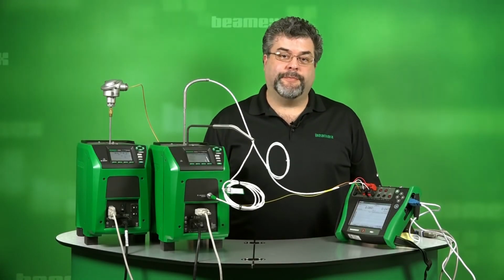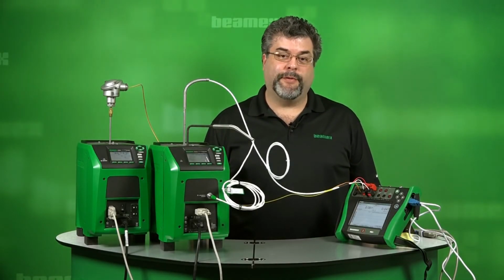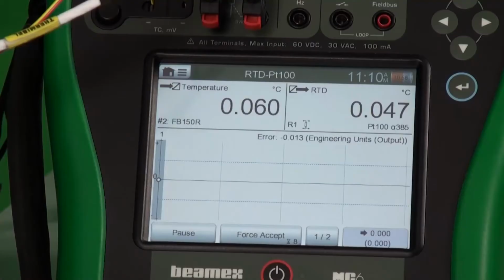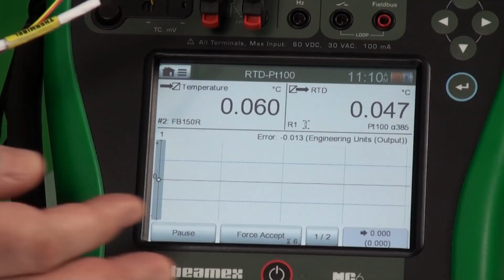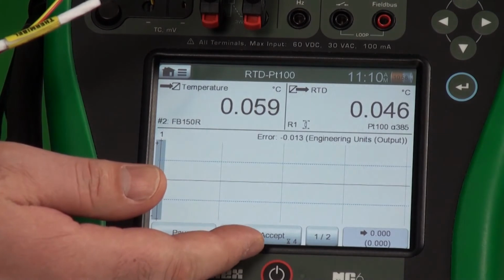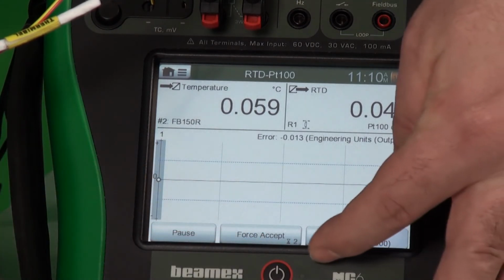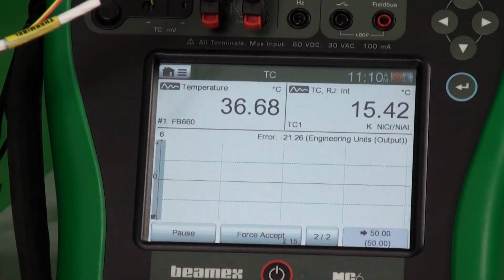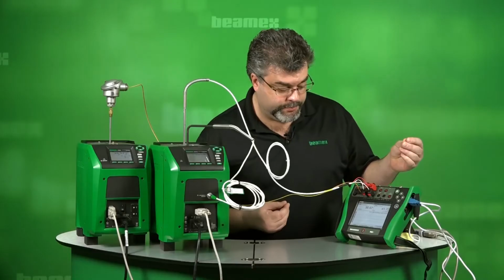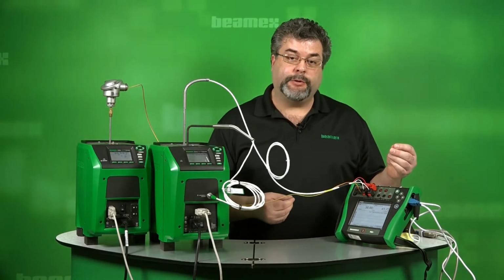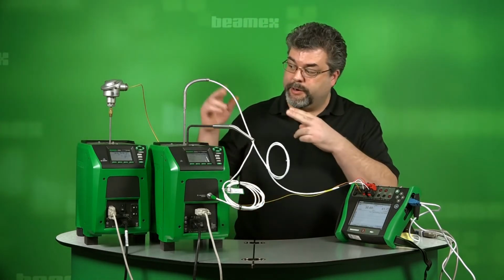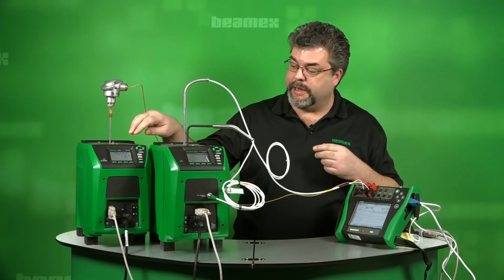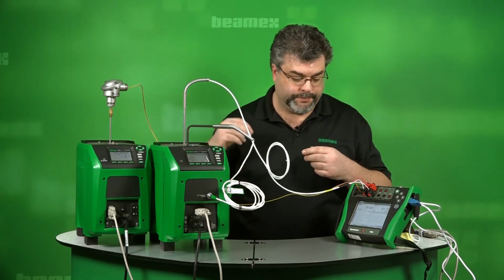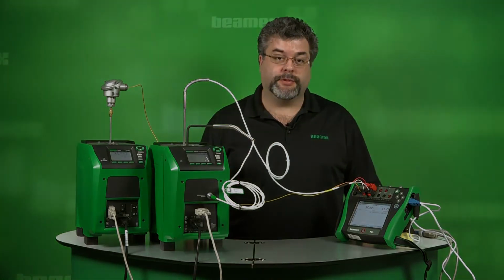We've just reached the first test point of the first dry block. We're testing our RTD. We have a 15-second delay built in. And you'll notice that we're also on tag number 1 of 2. So what will happen here is it will grab the test point. It's actually just done that. Now it's working on test point number 1 of our second tag using our high temperature dry block. So now we wait for it to hit the temperature.